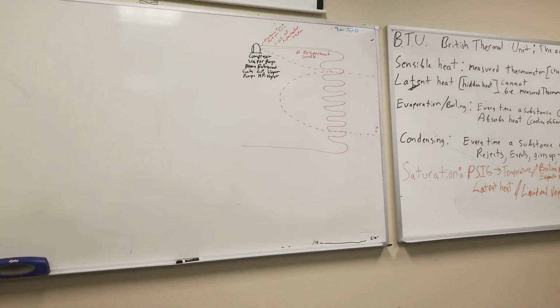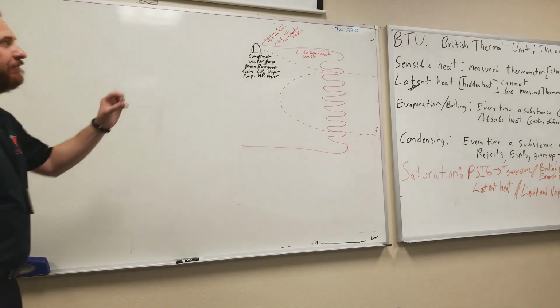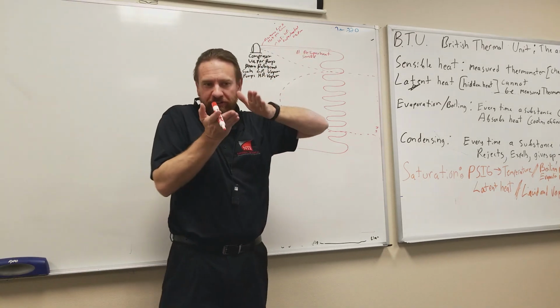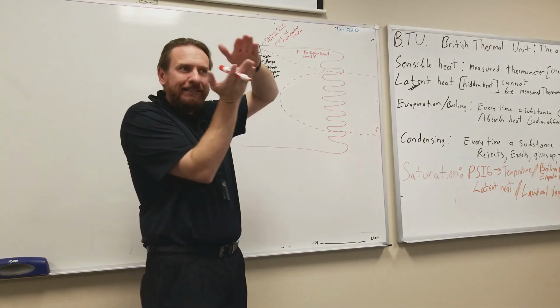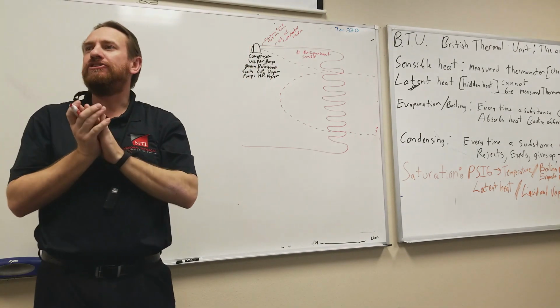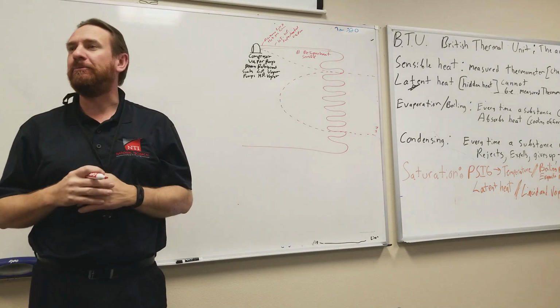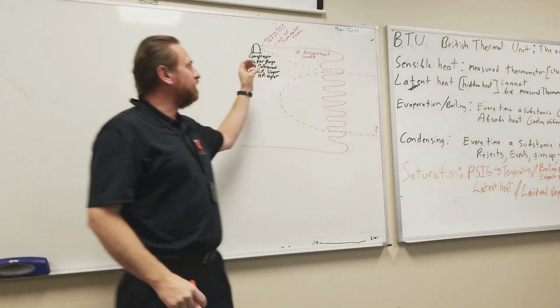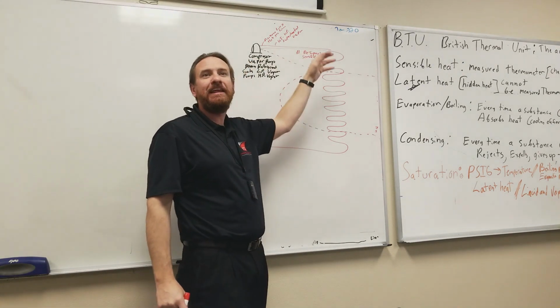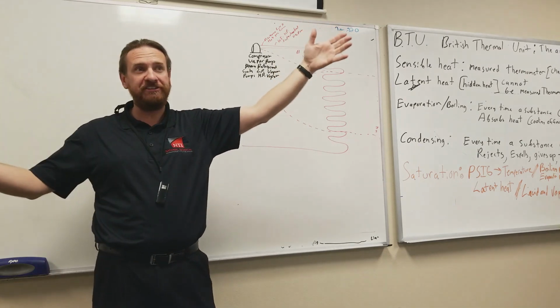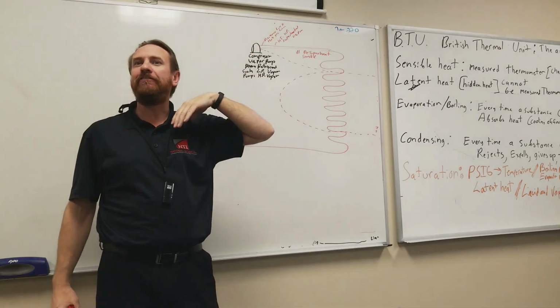So it doesn't have to be at saturation temperature when it enters the condensing coil? That's correct. And the very first section of that condensing coil, that little bit at the very top, doesn't take very much. The job is to de-superheat it. It's going to be all vapor, superheated vapor. So we have to take the heat out of that. We have to literally cool that. If it was steam, we have to cool that steam off first.